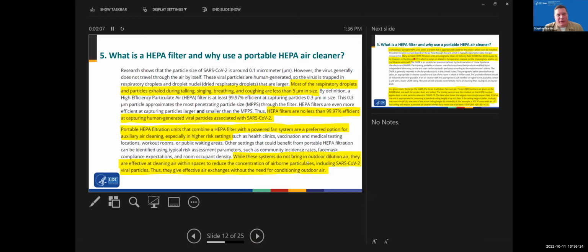So anyway, what is a HEPA filter? Throughout the pandemic, everybody's talked about what a HEPA filter is. By definition, HEPA filters are at least 99.97% efficient at capturing 0.3 micron particles. One myth I want to put to rest is that you'll hear a lot of people, particularly those selling other air cleaning products they want to compare to a HEPA filter, say that a HEPA filter is only good for particles down to 0.3 microns. That simply is not true. The 0.3 micron size is the most penetrating particle size through a HEPA filter, so it is more efficient than 99.97% at filtering particles that are larger and smaller than 0.3 microns. So if you hear that, you'll know that's false.